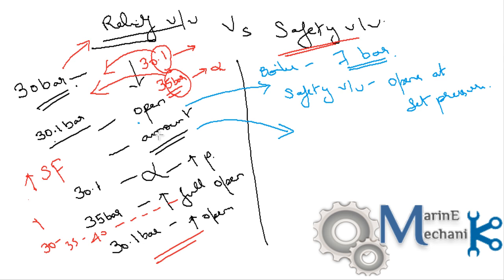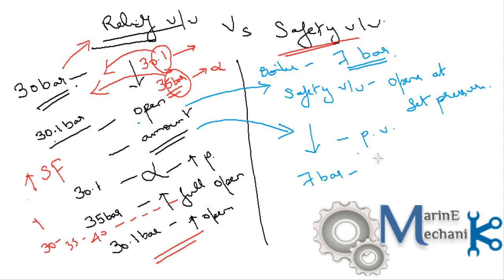The safety valve also has a spring and valve housing, but the amount of opening is huge — whether at 7 bar, 7.1, or 7.5, the opening is large enough to create sufficient pressure drop within the pressure vessel. When the safety valve opens at 7 bar in a boiler, it stays open until a sufficient pressure drop is achieved inside the boiler so it can operate safely, and will reseat at approximately 6.7 bar or lower.